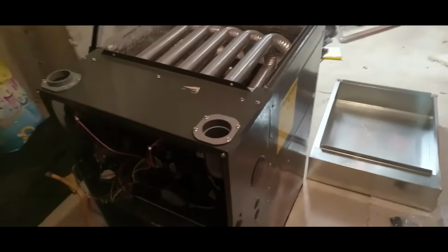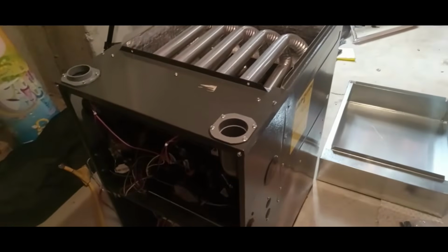So when we put that box underneath, we're lifting the unit up and we're allowing more air to flow in underneath the blower. And that really helps prolong the life of the unit. So we're going to do that now. We're going to flip this upside down, take the sheet of metal off the bottom, connect that box, and then we'll be ready to slide it in. We'll cut the return hole.